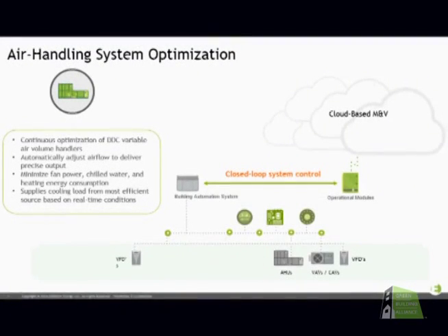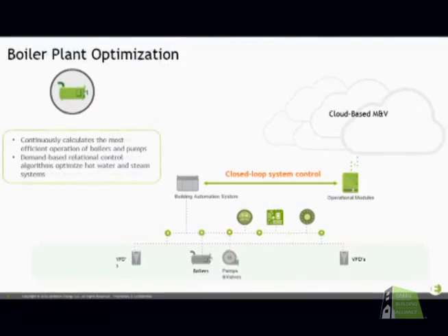And similarly for the air side system, most of what I said is applicable again. The operation's a little bit different for air side and boiler side systems. The components, typically you'll have definitely air handling units, and on most modern systems you'll also have VAV boxes that restrict that airflow, sort of analogous to a control valve on a water system, where you're just clamping down. And finally, boiler systems. So all components throughout an entire HVAC plant are able to be controlled in this way and monitored in this way.